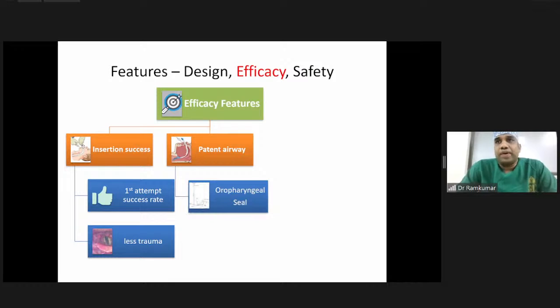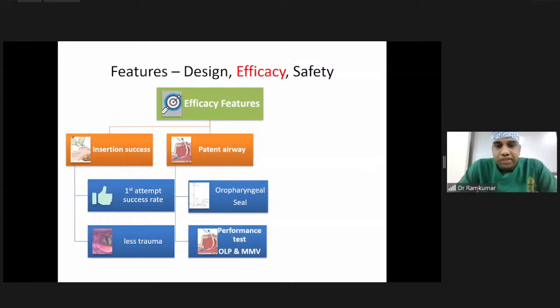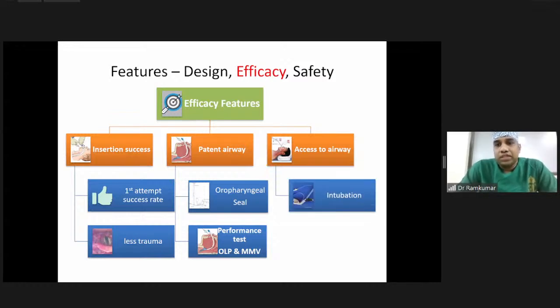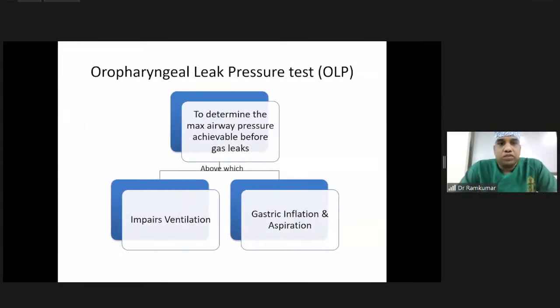And the next important thing is patency: how the airway patency is maintained, and the ventilation parameters. The important parameter is to assess the oropharyngeal seal, that is, you assess the oropharyngeal leak pressure. That is done by a few performance tests, which I'm going to show you later in subsequent slides. It's the oropharyngeal leak pressure or a minute ventilation test. Another is how you can gain access to the airway, that is, the chance of intubation through a device. All these help to assess the efficacy of a particular supraglottic device.